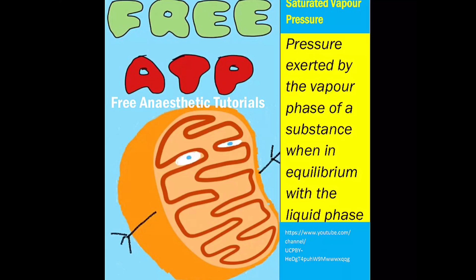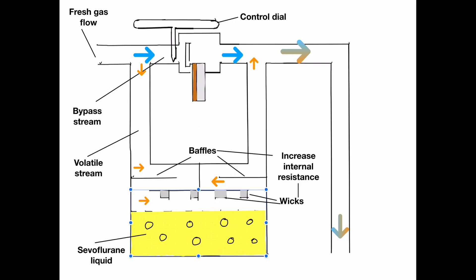It achieves saturation by a number of mechanisms. Number one: wicks and baffles. These ensure that the gas flow is slowed, maximizing contact area with the volatile, giving the volatile every chance to vaporize and join the fresh gas flow. These wicks and baffles significantly increase the internal resistance to flow of the vaporizer. The saturated vapor from the volatile stream then rejoins with the fresh gas from the bypass chamber, which dilutes the volatile concentration to an appropriate and safe amount to maintain the desired level of anaesthesia.